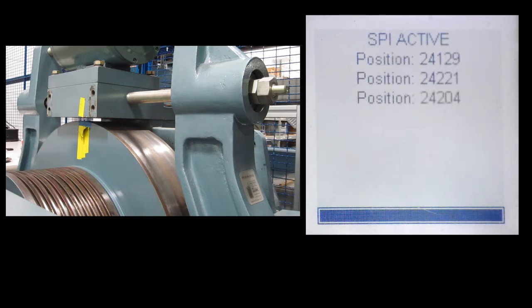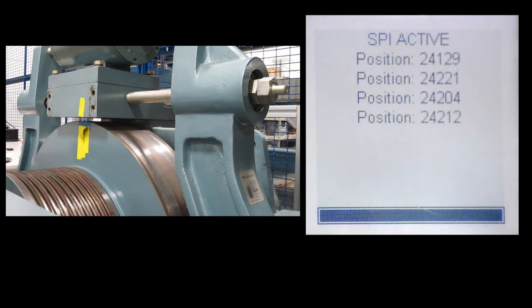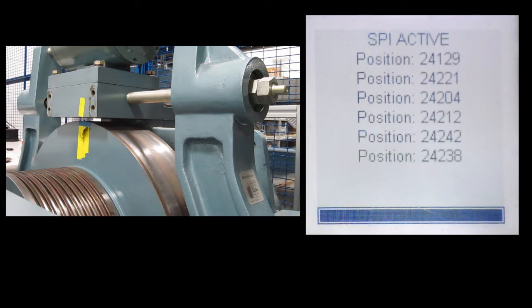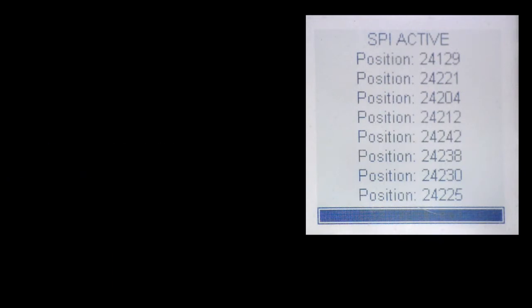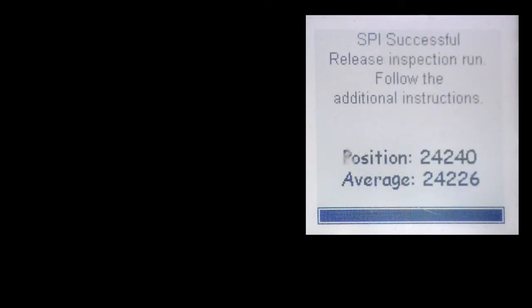As shown, the drive will take various encoder position samples. The drive is looking for consistency in the samples, where each sample should be relatively a few hundred counts from each other. During each sample, you'll generally hear a little chirp out of the motor.